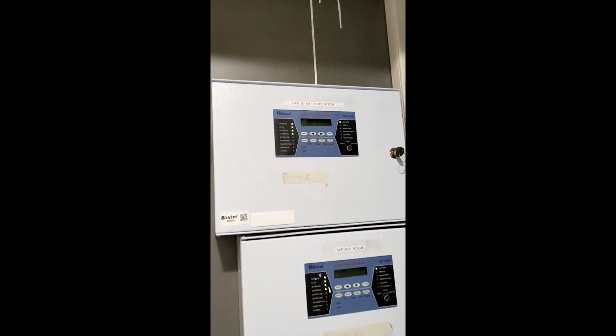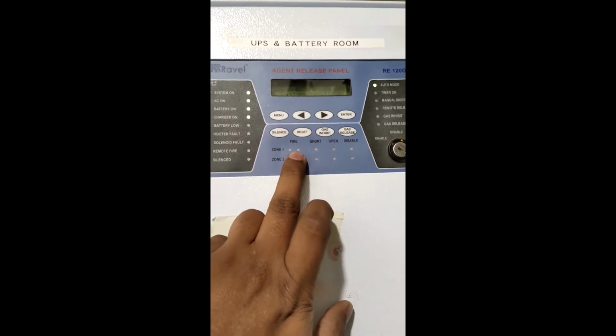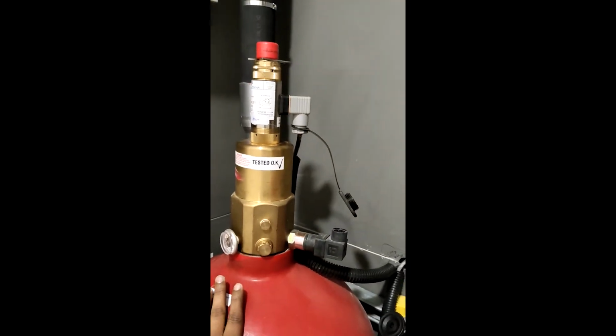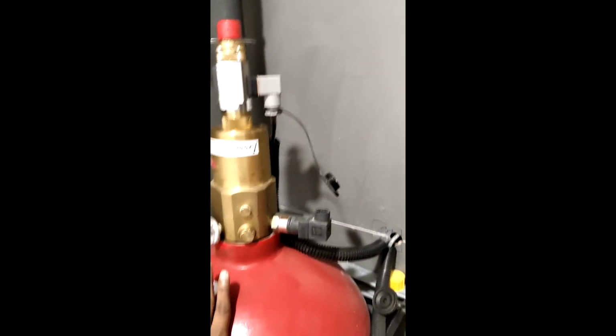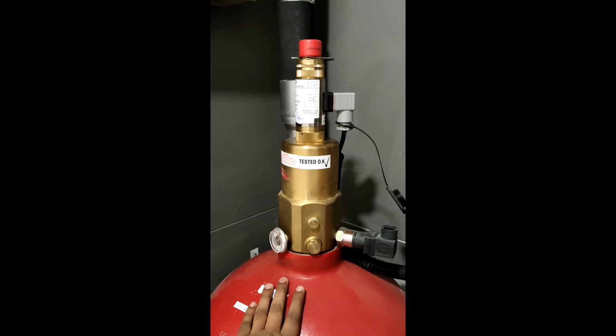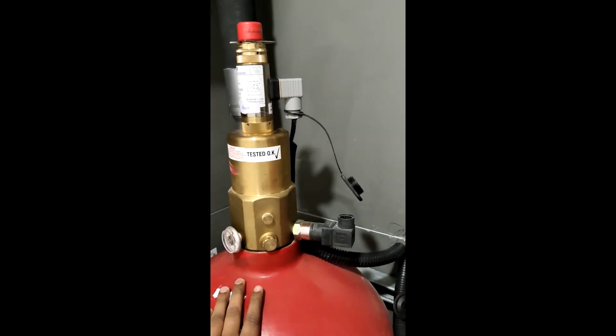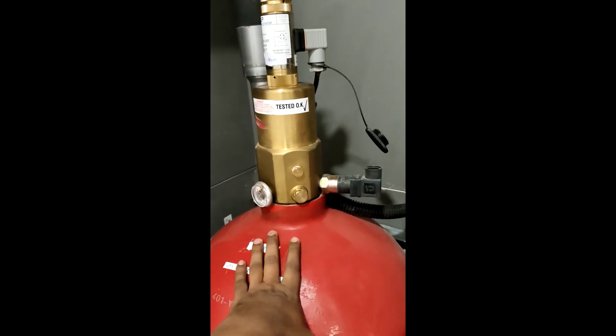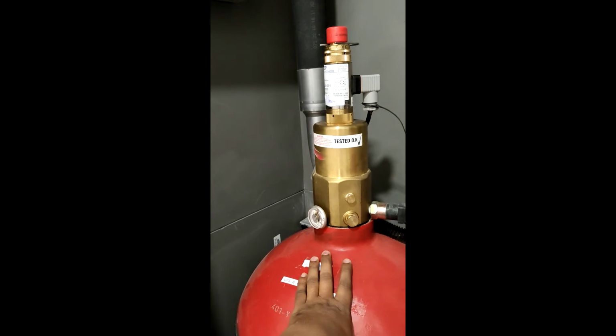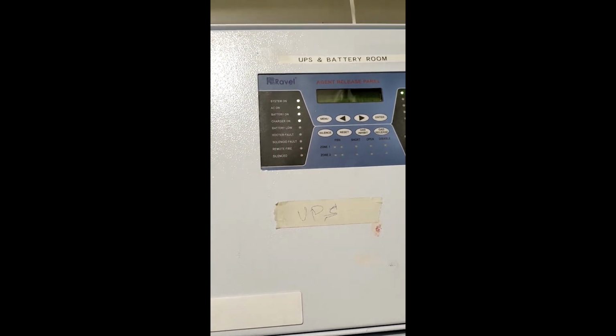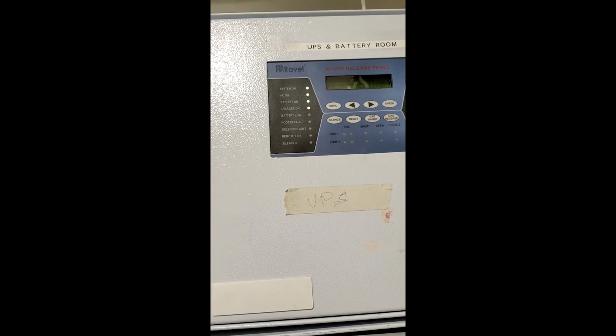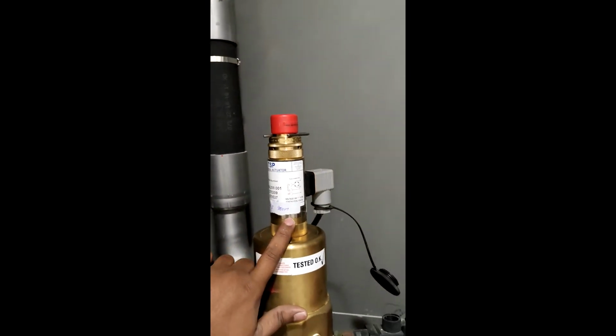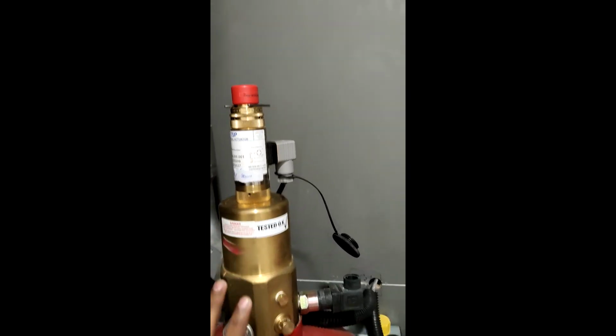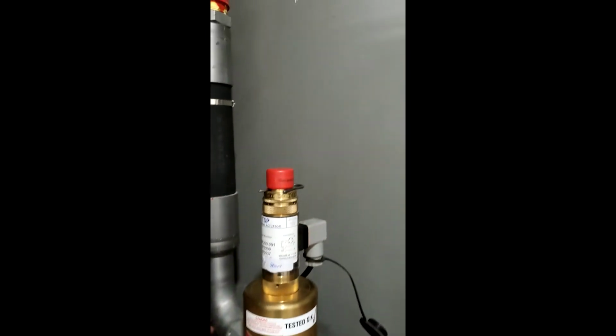Okay, in case zone 1 gets a fire, this cylinder will not get activated. Because in case of false alarms, this gas is very costly, so we don't want to simply waste the gas. So we have configured a double activation, in the sense that zone 1 and zone 2 both should get activated, and only then will this actuator get activated. When this actuator gets activated, the cylinder gas will come out of the cylinder and go through this pipe to that area.